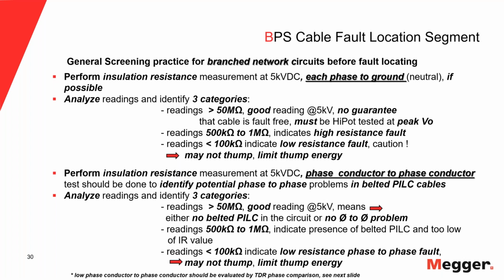So that's low, okay? But if you have a high reading, that means you have a good chance to get a flashing fault. The same thing applies if you have a really low resistance fault. It might not thump, and if it still thumps, you will be very careful how much energy you dump in that fault, and not the old-fashioned way: crank it up till you get more oomph. That might be just the worst thing you can do in that situation. So the insulation resistance gives you an indication where you are.